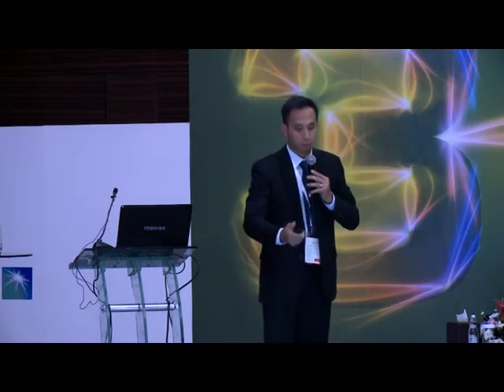So here is a typical facility one-line diagram. We still have the air magnetic breakers and electromechanical relays. If you're familiar with this equipment, you'll probably be able to tell what kind they are. The feeder breakers are the same, air magnetic, and the feeder relays would be the same. So imagine you were working on, let's say, one of the feeders, racking it in or racking it out, and for some reason it fails. You're pretty much relying on this relay to pick up that fault, and then relying on this breaker to clear, to open, right, to interrupt the fault. So going back again to the clearing time, it's a very big factor.